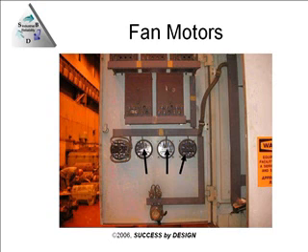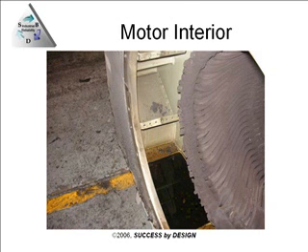So the arrows in this particular picture are pointing to the back of the current indicators, the analog current meters on the face of the control. What we did is we attached a clamp, the instrument CT, to each one of these and took our data. So the data I'll show you will have current only, no voltage. The first machine had failed.